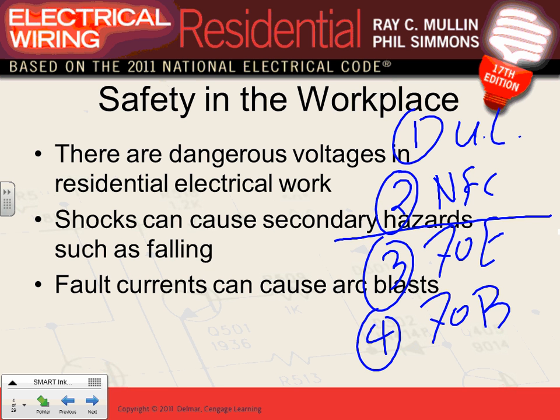The boundary is 4 feet. Boundaries of arc flash typically are 4 feet unless you calculate it. But 10 feet is the safest. At 10 feet you go home with nothing on you. At 4 feet you might get burns.